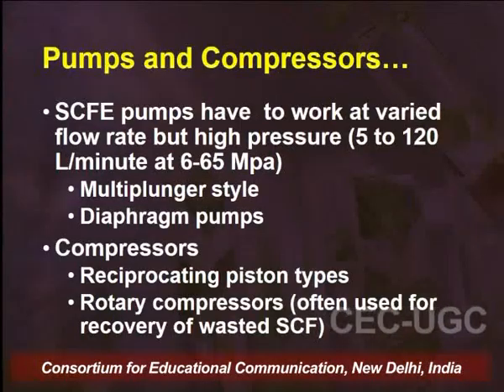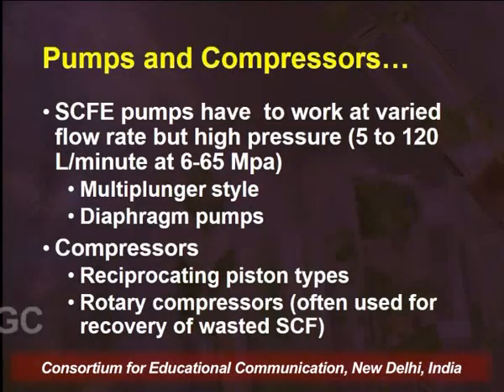Now, if we talk about the basic mechanism of the pumps and the compressor, we can categorize the pumps into two major types: multi-plunger type pumps and diaphragm pumps. As the name indicates, multi-plunger pumps have multiple plungers in their structure which keep on pumping the solvent, or which keep on reciprocating with each other, to provide a pulseless flow of the solvent, and they also help in maintaining the pressure. Whereas diaphragm pumps work on an altogether different mechanism, and the major difference between multi-plunger and diaphragm pumps is the use of lubricants.